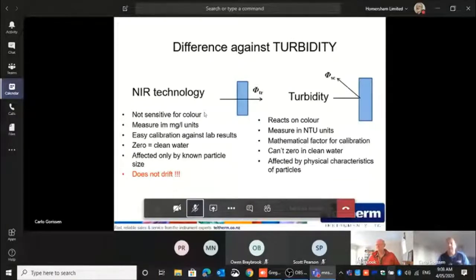Clean water for us is 0. So you put it in a glass of water, it should be 0. Very easy. You normally don't have to do that with commissioning, but after a few years, we always tell people to once in a while check it in clean water, because you could have fouling on the sensor, on the surface of the glass, and then of course your 0 is off. But it's very easy to see that.